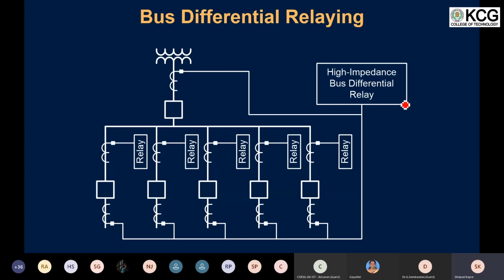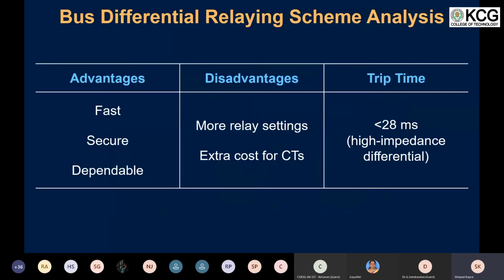If the fault were to happen on the outgoing leg of the feeder, then the system is pretty much balanced, because the incoming current is distributed among all the outgoing feeders, and the summation of the incoming and the outgoing is going to be zero. But if the fault were to happen on the switchboard where the person is working, or on the breaker where the person is working, then the system would see that as a differential current, and the differential scheme would operate and trip all the breakers associated with the fault. But in this case, there is an extra cost associated with the CT, and there is an additional relay requirement to do this high impedance differential scheme.